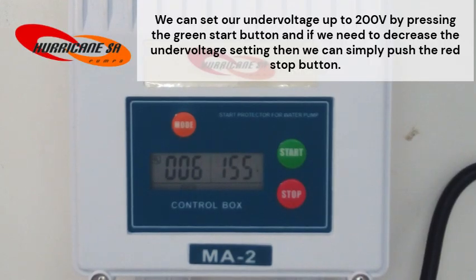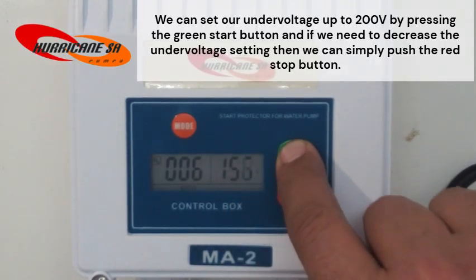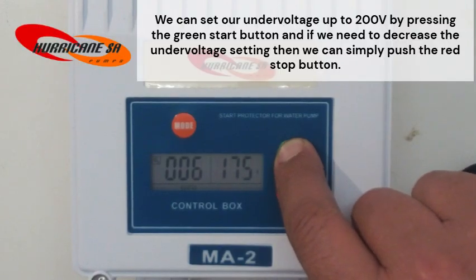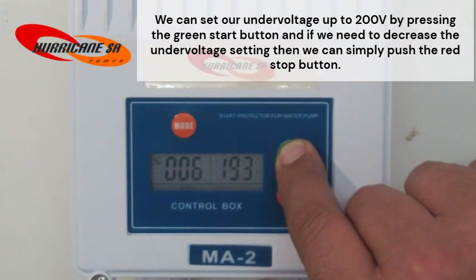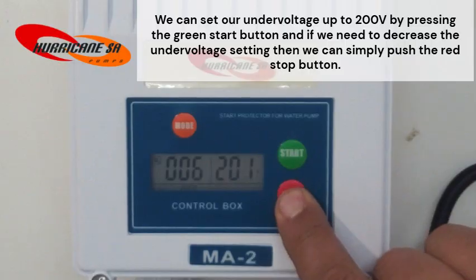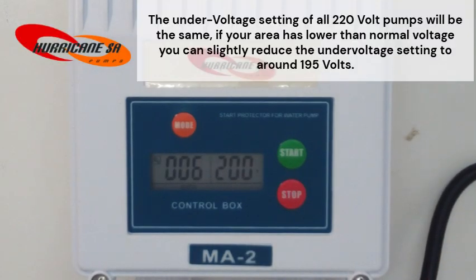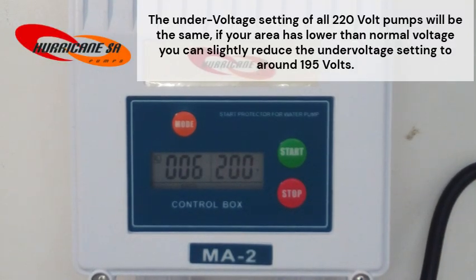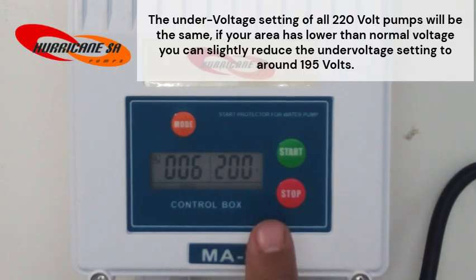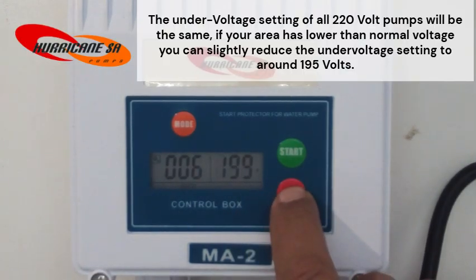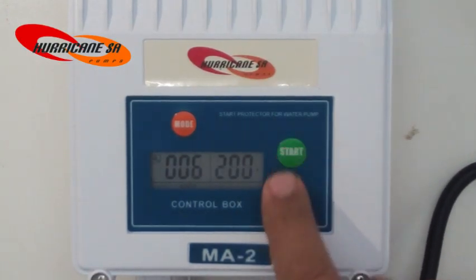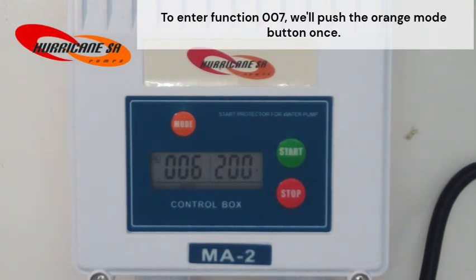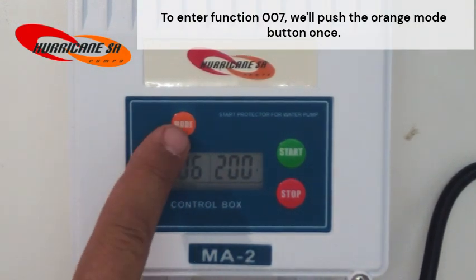We can set our undervoltage up to 200 volts by pressing the green start button. And if we need to decrease the undervoltage setting, then we can simply push the red stop button. The undervoltage setting of all 220 volt pumps will be the same. If your area is lower than normal voltage, you can slightly reduce the undervoltage setting to around 195 volts. To enter function 007, we'll push the orange mode button once.